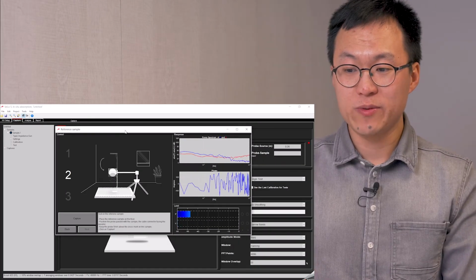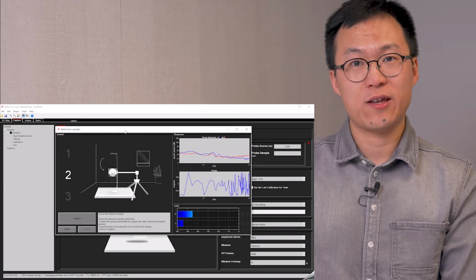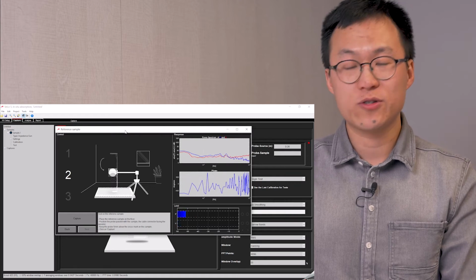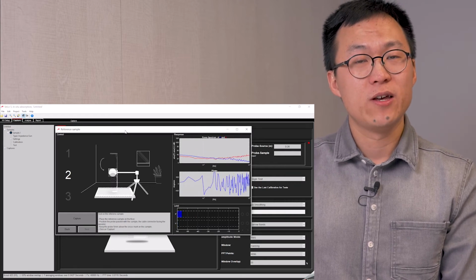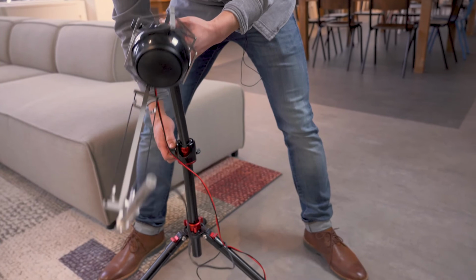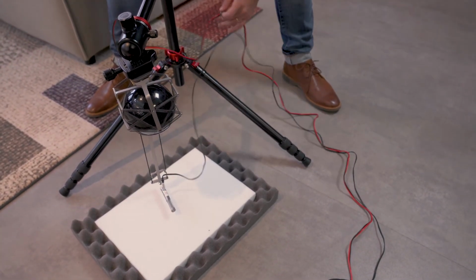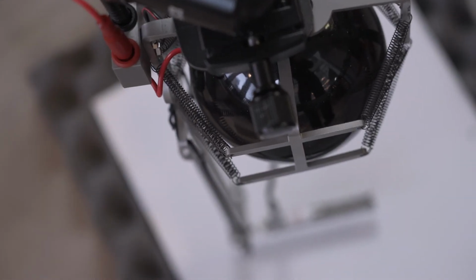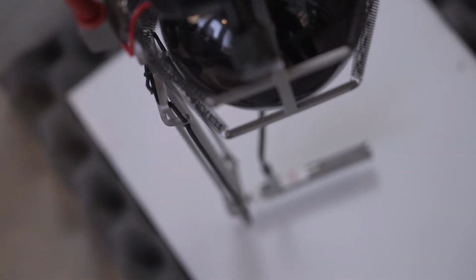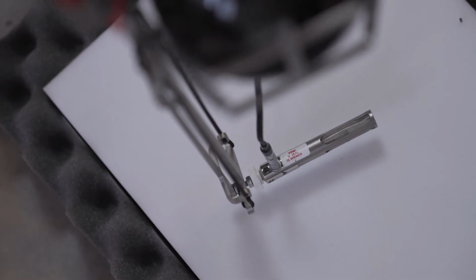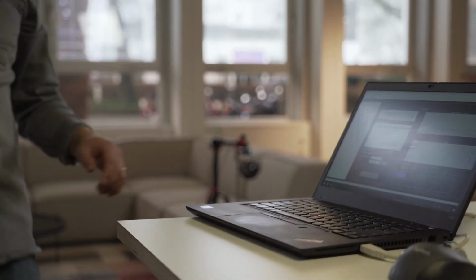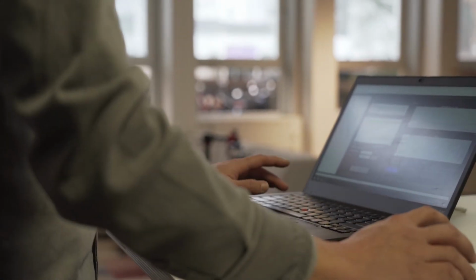After the calibration measurements, the software jumps automatically to the second step, which is to test on the reference sample. What you have to do is to rotate the setup and put the probe parallel to the sample surface, with the cable connector facing the loudspeaker. Now the probe has to be 5 mm above the center of the sample, and then we can click on the capture button.